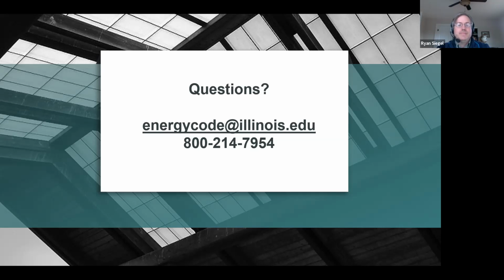Okay, looks like we've got most of our responses in for our poll. Looks like most people have picked up that ASHRAE is more stringent on service water heating requirements for load calculations and temperature controls. Pool covers is a little iffy, although we tend to lean towards ASHRAE since it requires both indoor and outdoor pool covers, even if the temperature requirements are a little bit different, a little less stringent. But pipe length is more stringent in the IECC. ASHRAE does not have those pipe length provisions in them where the IECC does. So the first three there are the correct choices. The last one there is the IECC is more stringent.